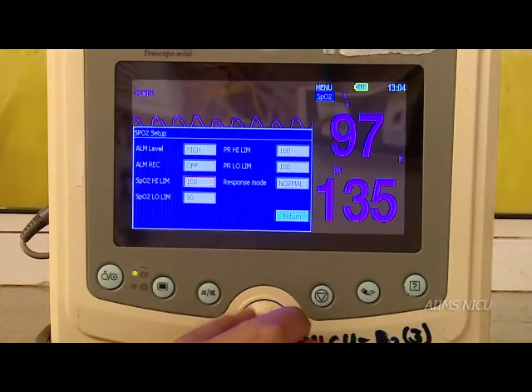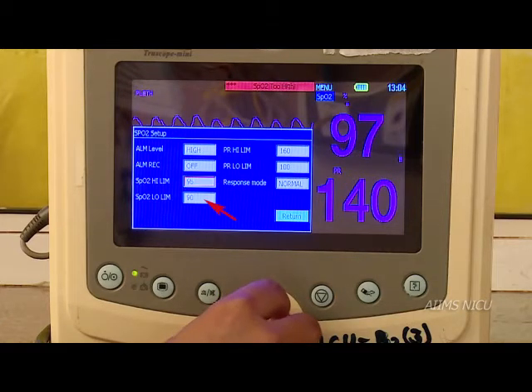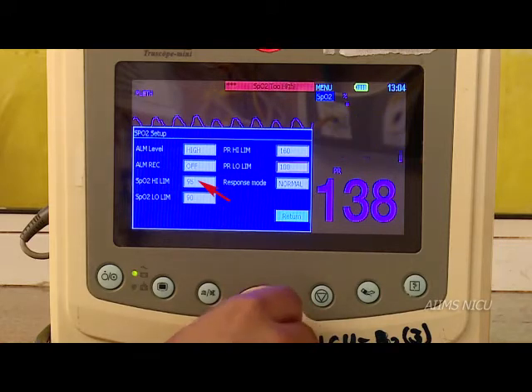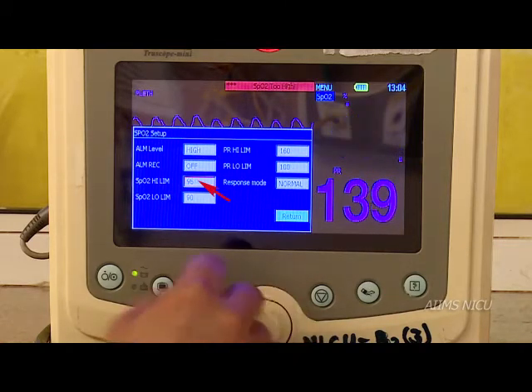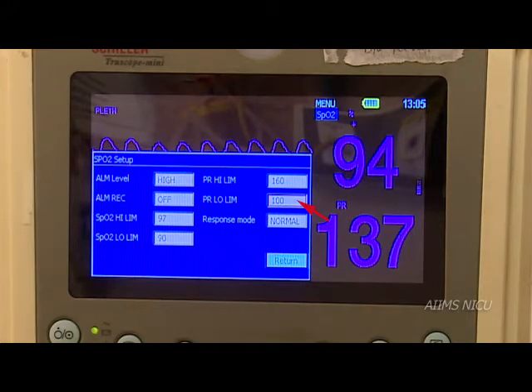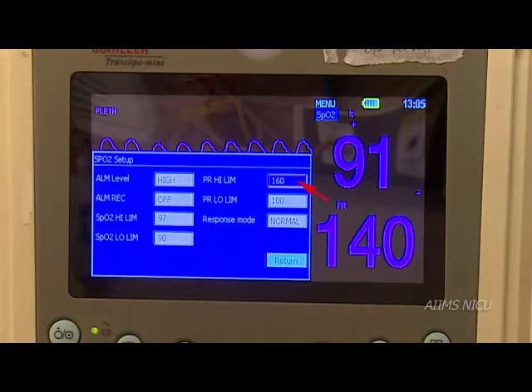Let us now try and understand how to set the alarm limits. For oxygen saturation, the lower limit should be set at 90% and the upper limit at 95% for preterm babies. For heart rate, the lower limit should be set at 100 per minute and the upper limit at 160 per minute.